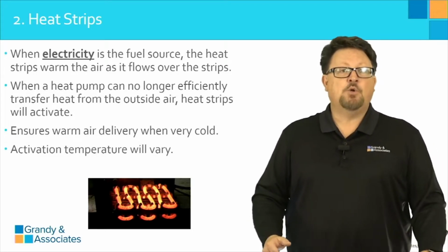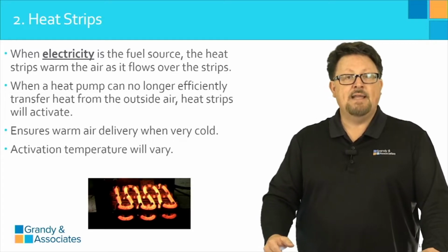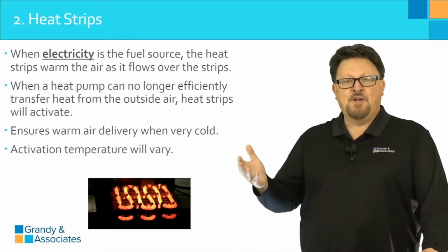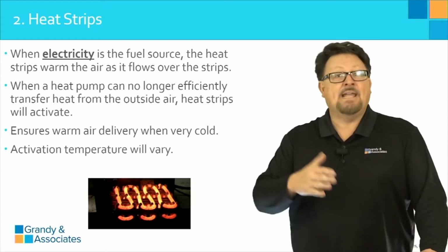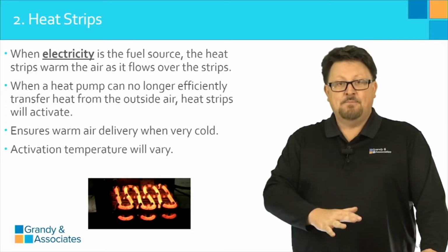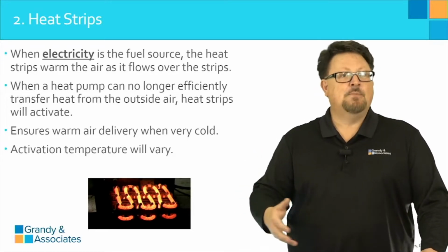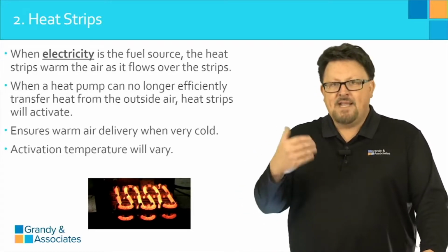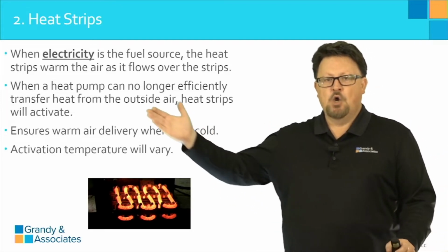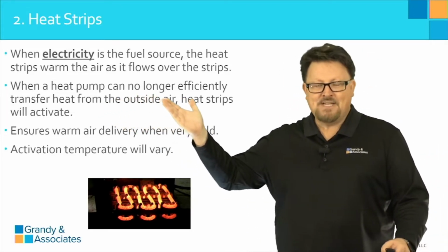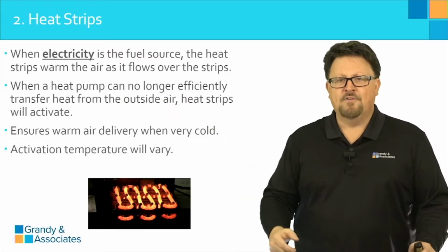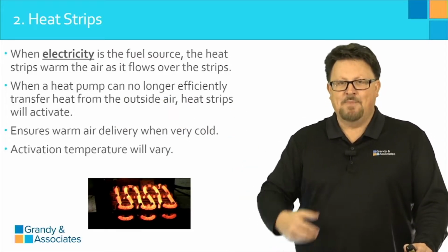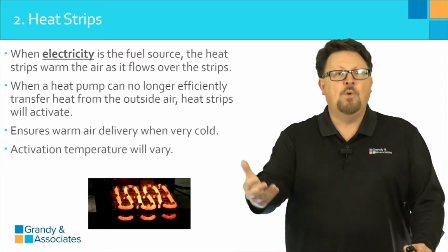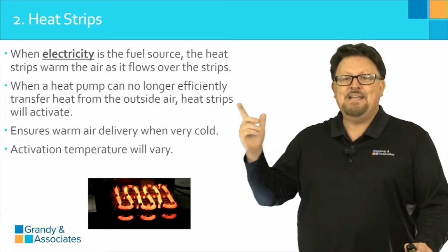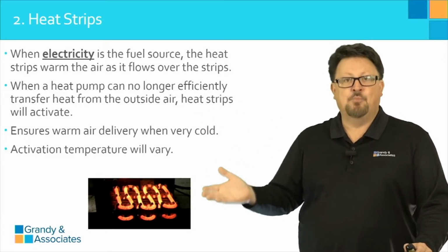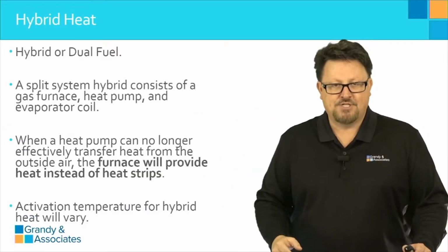That's a very common question that comes up in our live training. You know, what's the magic temperature where these kick in? It can vary by system, the stages of the system. A lot of factors go into that, but here's the guiding principle. Whenever that heat pump sitting outside can no longer efficiently transfer enough heat from the outside air to keep up with demand, then these heat strips will activate to provide the extra boost.